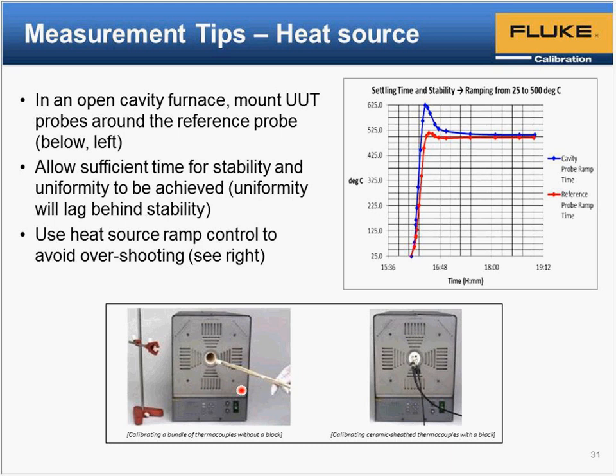Fortunately, the furnace is not impacted significantly by ambient conditions. If the ambient is unstable, the room temperature going up and down quickly, furnace stability could be impacted. The typical uniformity, which is the mean value we take from this, is not impacted by that, and the same thing goes for the reference junction. Hopefully it's insulated and isolated away from room temperature.